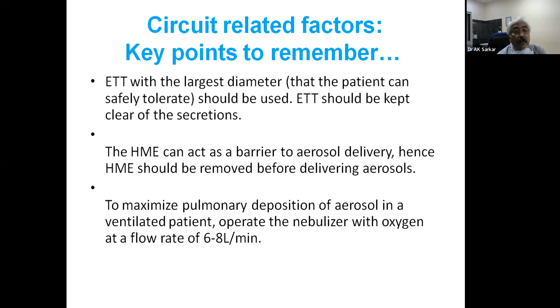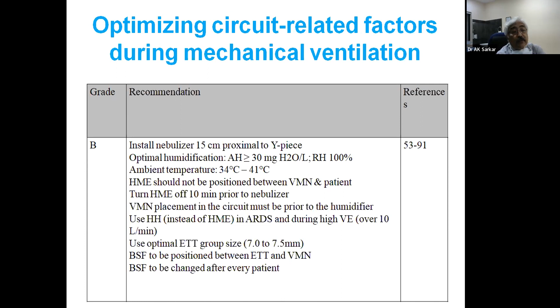Regarding circuit-related factors during mechanical ventilation, optimum humidification is achieved with a heated humidifier at a temperature of around 34 to 41 degrees centigrade. An HME should not be positioned between the vibrating mesh nebulizer and the patient. The vibrating mesh nebulizer must be placed in the circuit prior to the humidifier in the case of a heated humidifier, and use the optimal ET tube, which I have already mentioned.